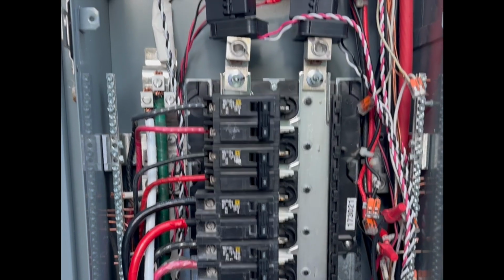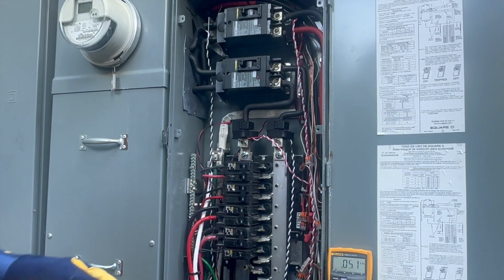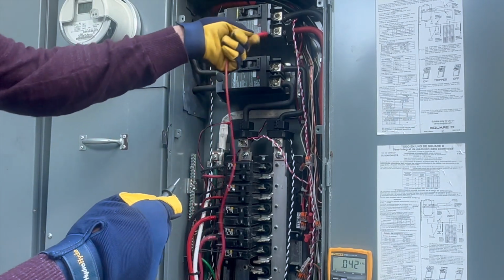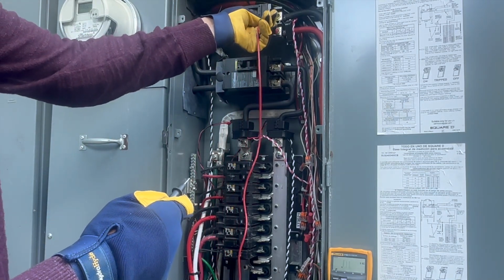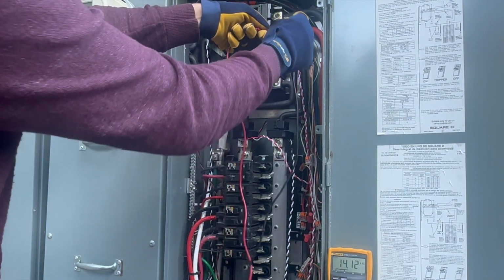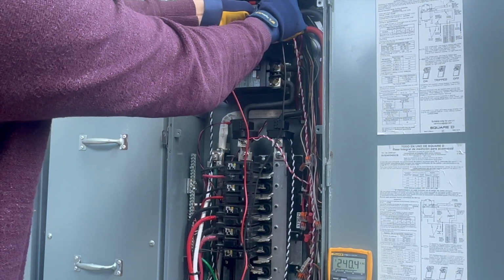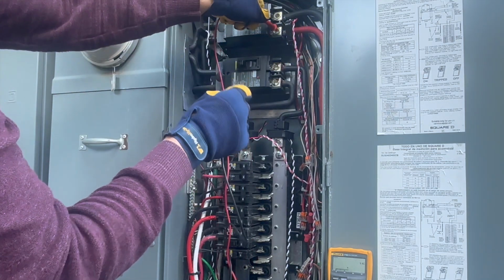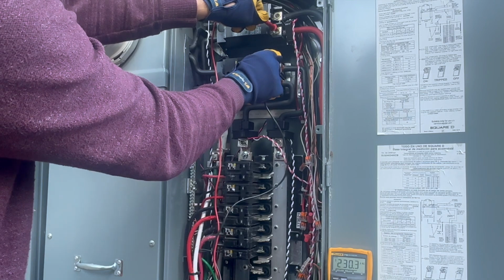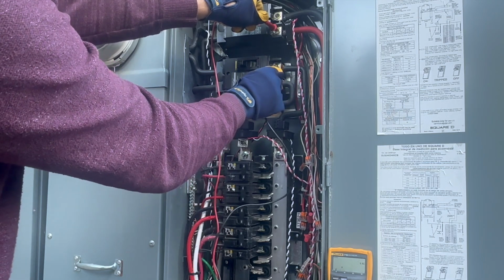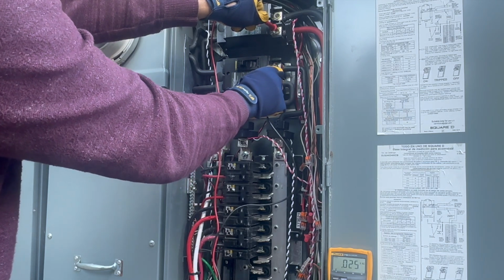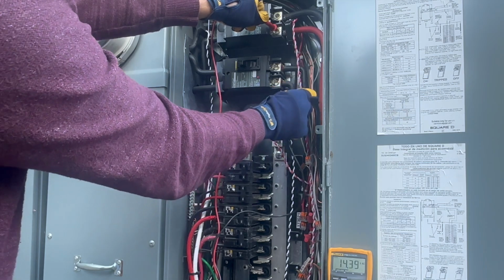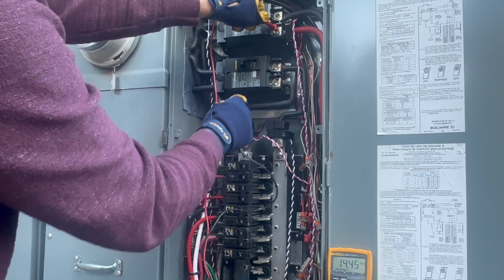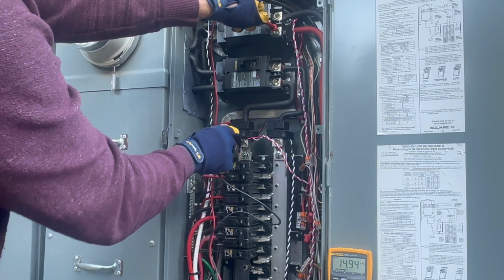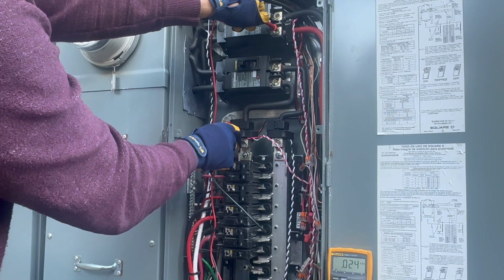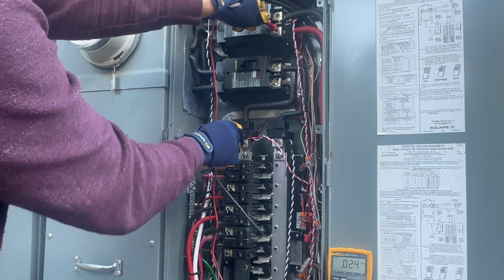But we really need to verify which bus bar is the same phase as the red wire on the top breaker. The red and black wires connected to that top 200 amp breaker are what run to the supply lugs in the Tesla Backup Gateway and define L1 and L2. We need the Tesla Backup Gateway to agree with these bus bars as to which carries red and black for the reference voltages for CT1 and CT2 to make sense. Let's do some more voltage comparisons and figure it out.